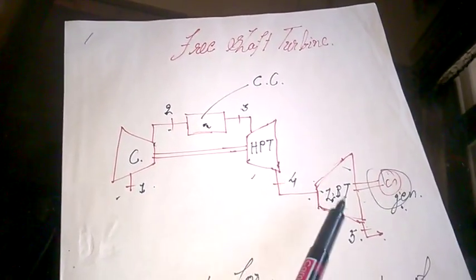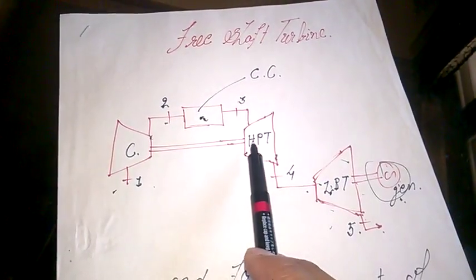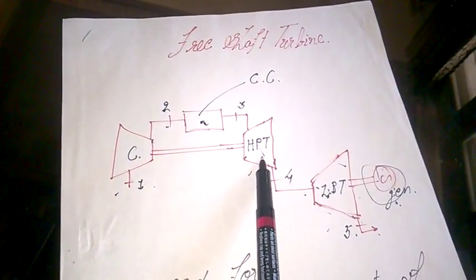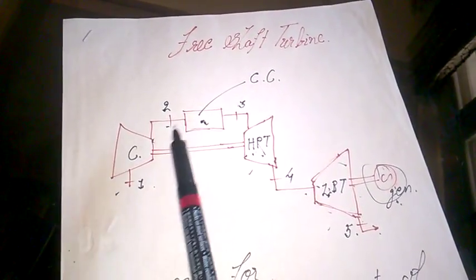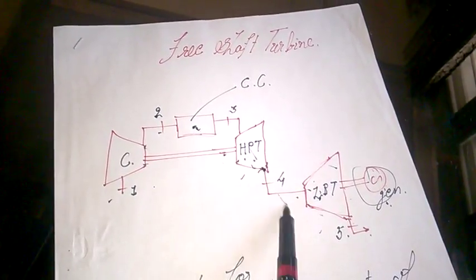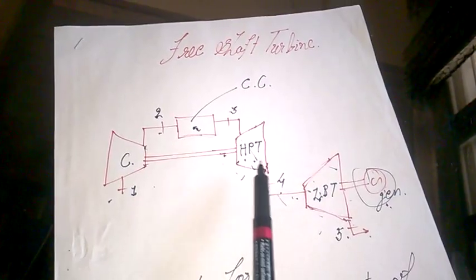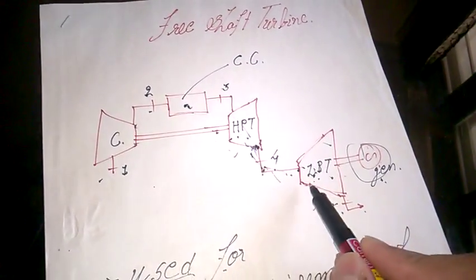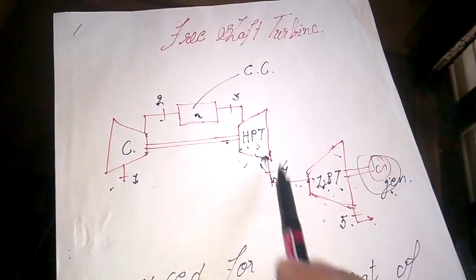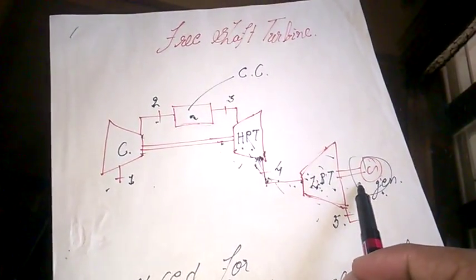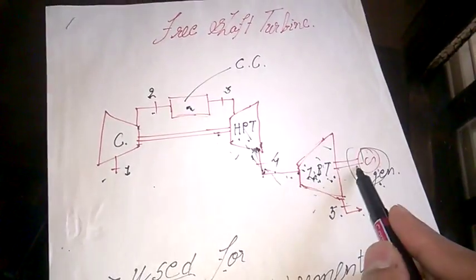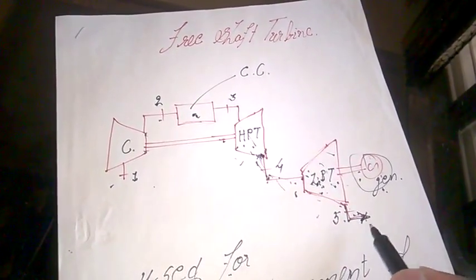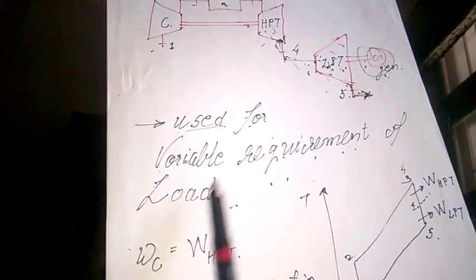We have two turbines: high pressure and low pressure. The air-fuel mixture burning in the combustion chamber enters the high pressure turbine, which rotates and gives power to the compressor. The extra exhaust gases — which still have some energy in terms of heat, temperature, and pressure — go into the low pressure turbine. The low pressure turbine rotates due to the exhaust from the high pressure turbine and generates the output power. The shaft of the low pressure turbine is not connected with the compressor, so it is the free shaft. The exhaust then goes to the atmosphere.